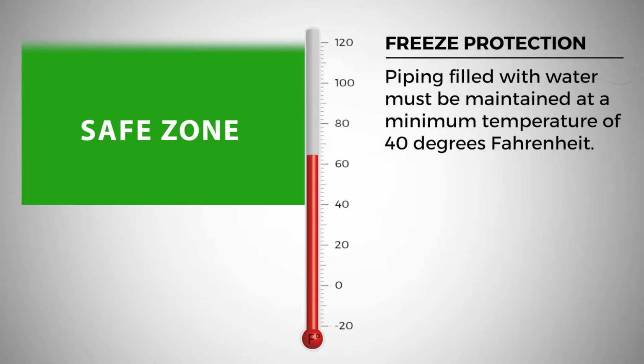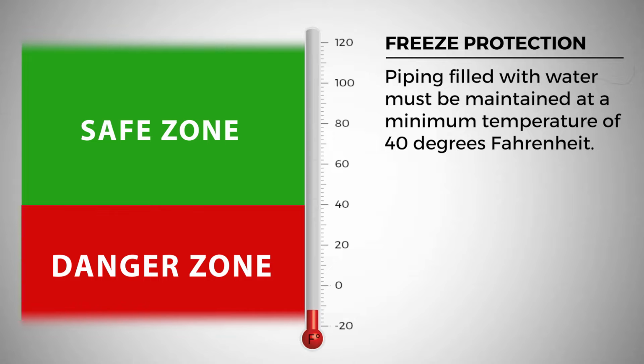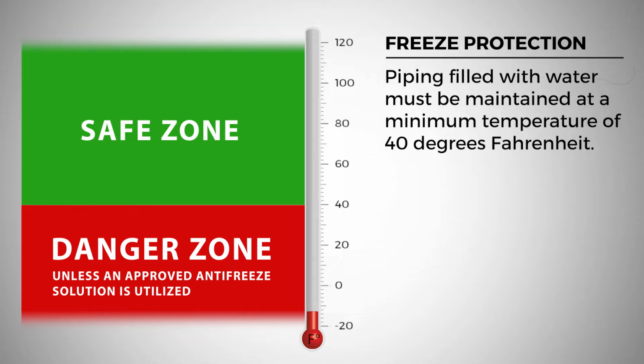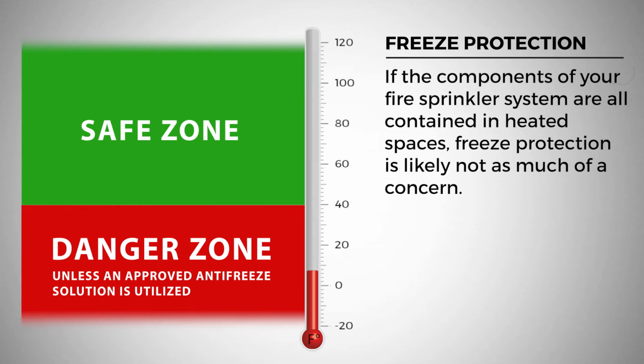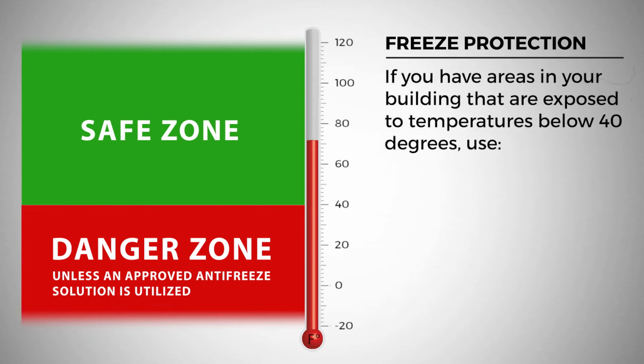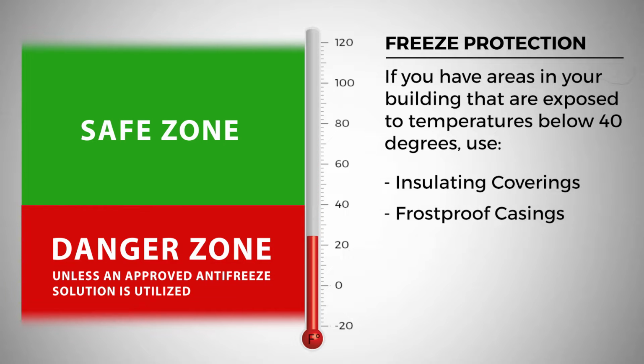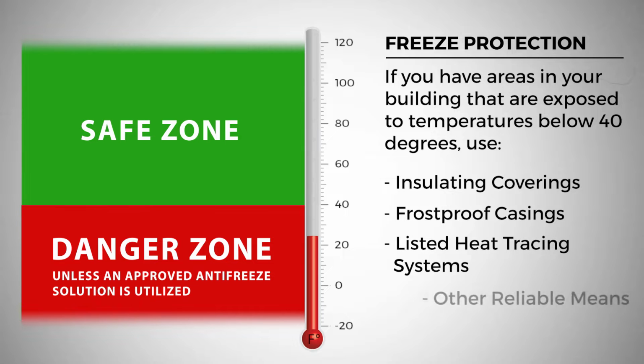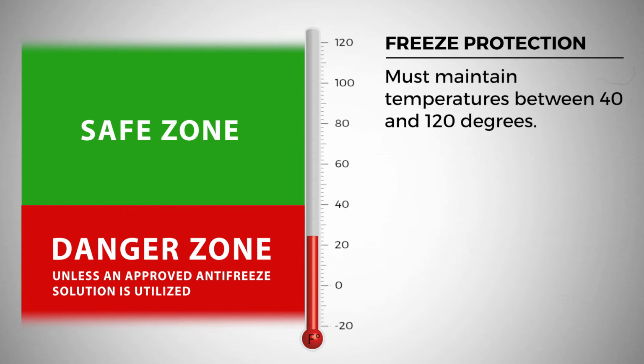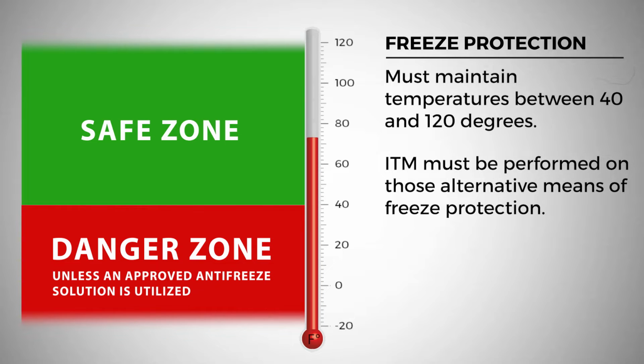Any piping filled with water must be maintained at a minimum temperature of 40 degrees Fahrenheit to ensure freeze protection, unless an approved antifreeze solution is utilized. If the components of your fire sprinkler system are all contained in heated spaces, freeze protection is likely not as much of a concern. However, if you have areas in your building that are exposed to temperatures below 40 degrees, insulating coverings, frost-proof casings, listed heat tracing systems, or other reliable means may be used. They must maintain temperatures between 40 and 120 degrees. ITM must be performed on those alternative means of freeze protection.